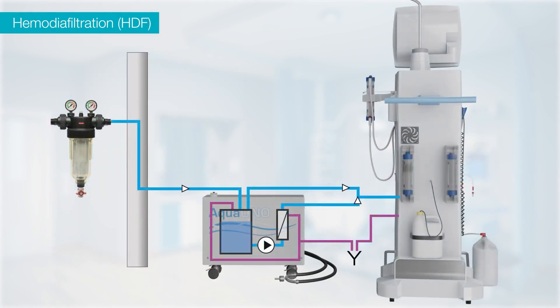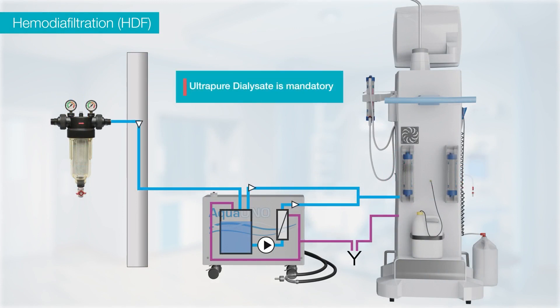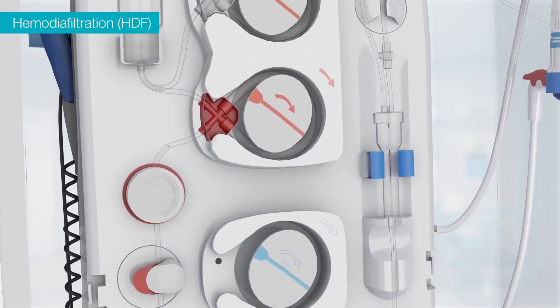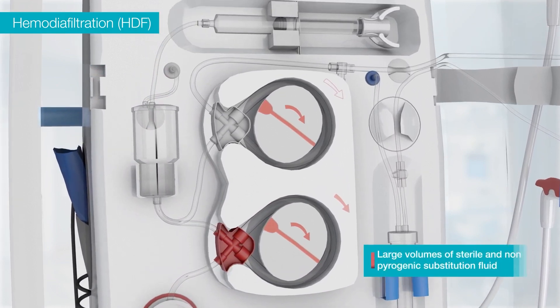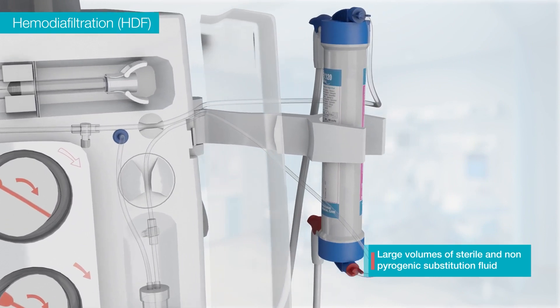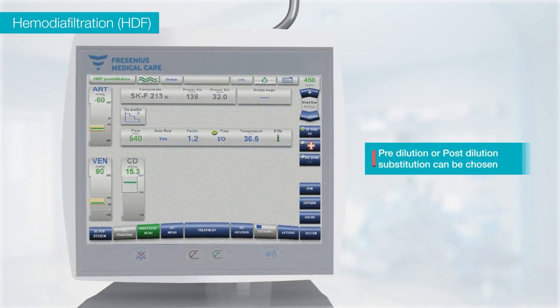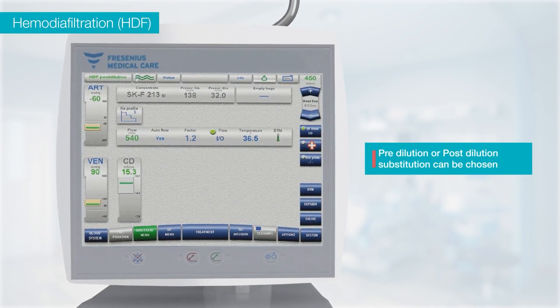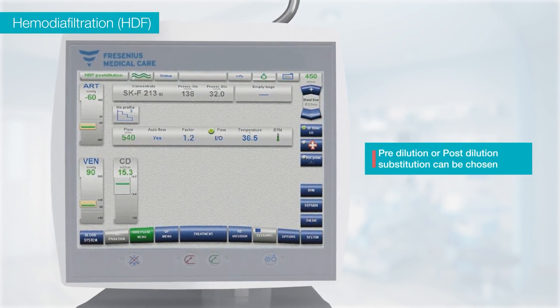For the online hemodiafiltration process in the 5008S, using ultra-pure dialysate is mandatory. The ultra-pure dialysate can be processed by using the Aqua UNO-RO system with endotoxin retention filters. The online hemodiafiltration process involves creation of large volumes of sterile and non-pyrogenic substitution fluid through a second endotoxin retention filter. Either pre- or post-dilution technique of substitution can be chosen as per the patient prescription, while post-dilution is the preferred modality worldwide.